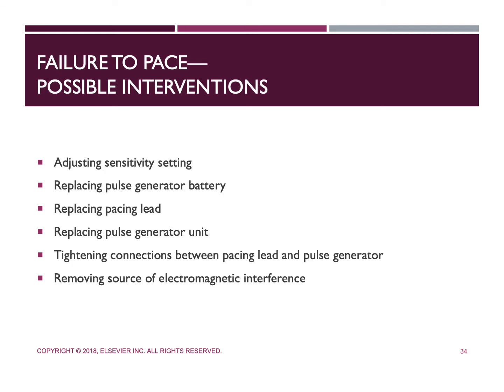Treatment may include adjusting the sensitivity setting, replacing the pulse generator battery, replacing the pacing lead, or replacing the pulse generator unit, tightening connections between the pacing lead and pulse generator, or removing the source of electromagnetic interference.